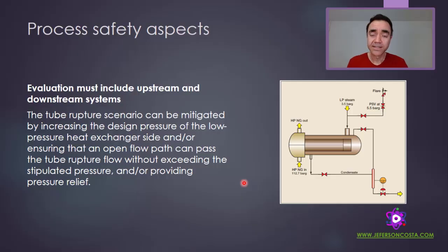One point of attention here is that for this exercise, I considered the maximum operating pressure of the high pressure side. But a more conservative way to apply this rule is to consider the design pressure of the high pressure side.